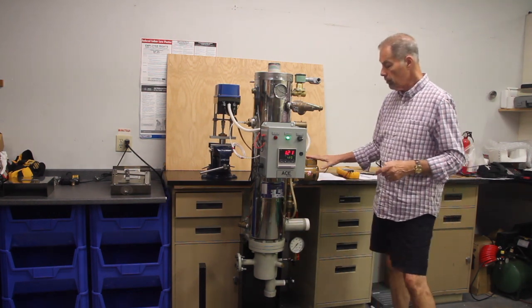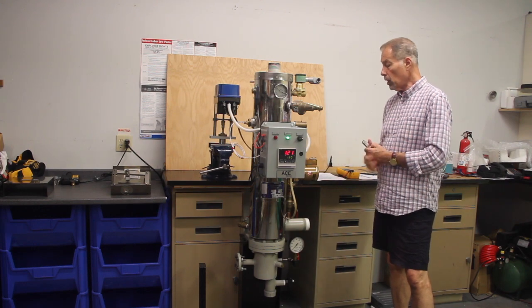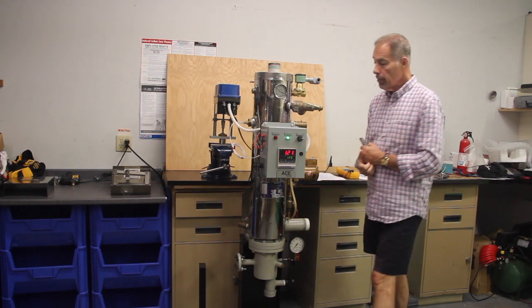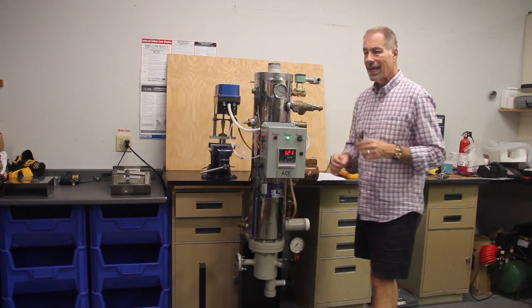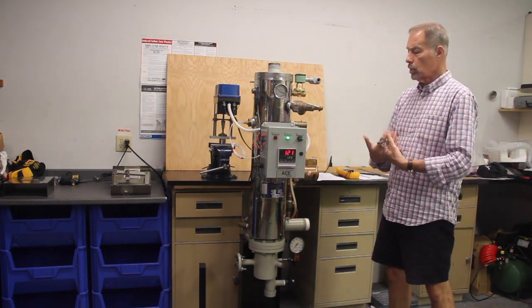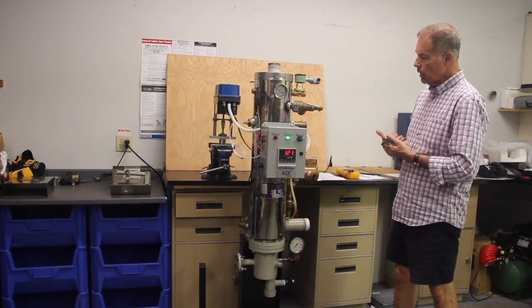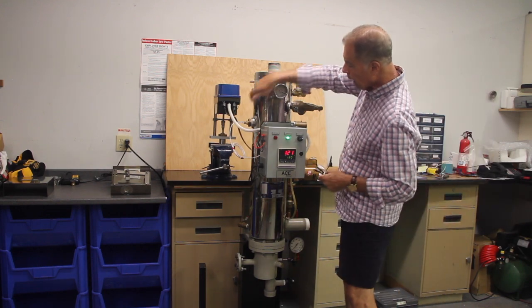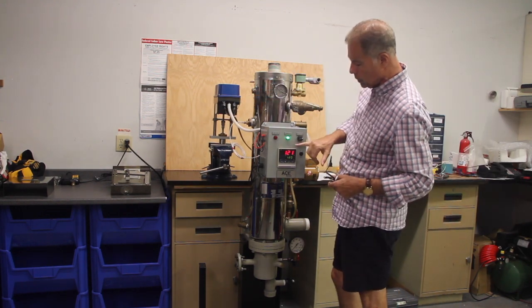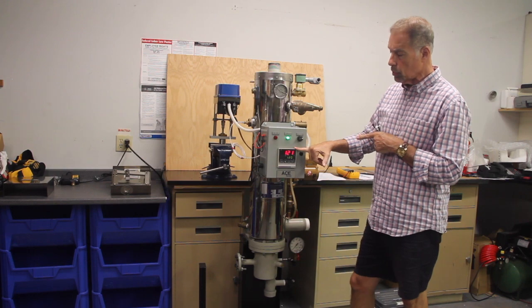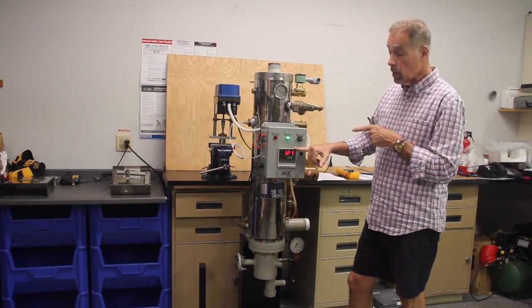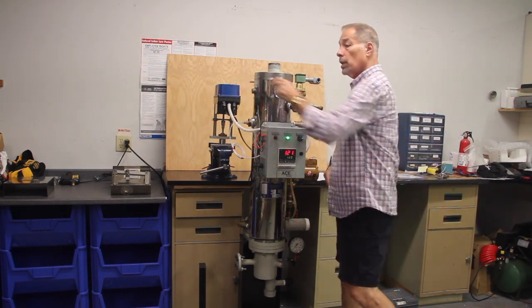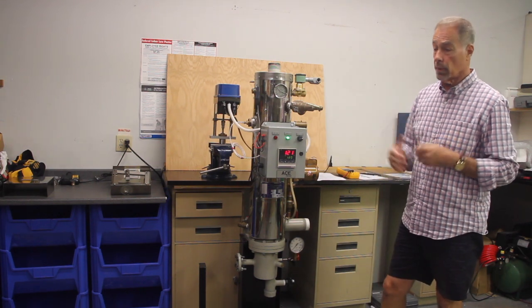This pump is critical. It runs all the time. It's designed to run all the time. And that maintains a very, very tight, what we call anticipatory temperature control on the heater. Because if you have good signal in from this RTD into this microprocessor controller, you're going to have very good signal out to the actuator, and you're going to have very tight temperature control.